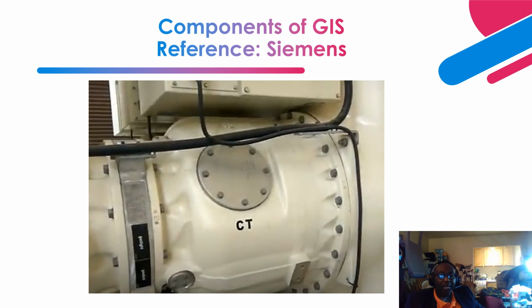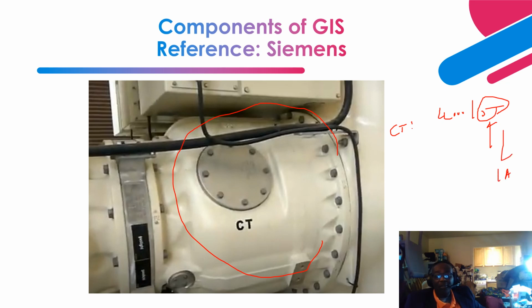So for the current transformer, this is the enclosure of the current transformer. So the CTs that you have, let's say you have a 4000 is to 5 CT, right? The relay or the metering circuit needs only 5 amps, right? And sometimes you can have a 1 amp CT on the secondary side current for your meters and your protective relays. Okay, so this is in close proximity, in series with your circuit breaker. This is basically your sealing end. Okay, so this is the gas tight barrier that basically differentiates this section, protects this section from this section.